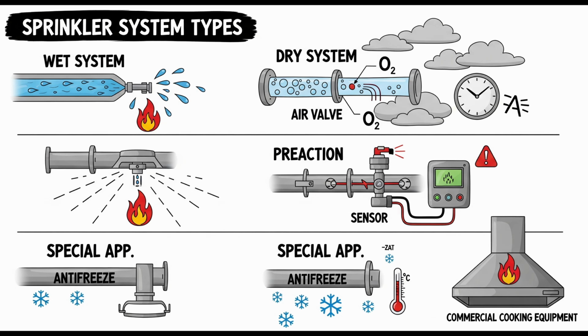And if a backflow preventer is used, the setup must include a way to perform a full forward flow test of the backflow preventer itself, according to the testing standard, NFPA 25, or specifically 16.145, ensuring it's working correctly and not stuck or leaking. Makes sense. Test the safety device. If a backflow preventer is used, the source requires a listed expansion chamber. What's that for? This is a crucial component whenever you have a check valve or backflow preventer creating a closed section of piping filled with liquid.